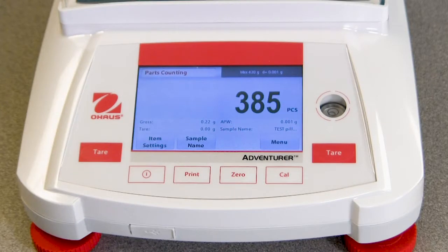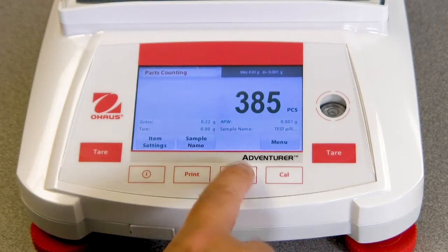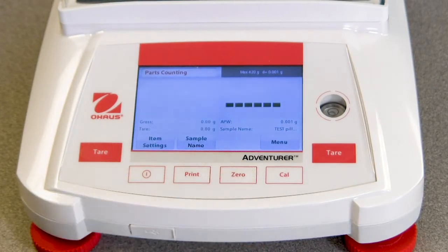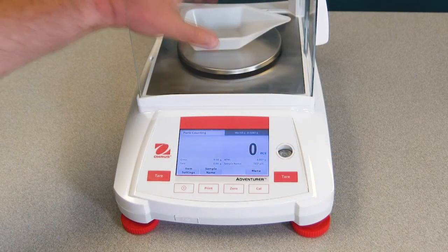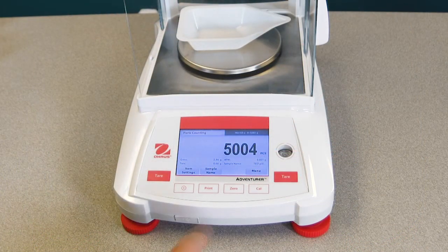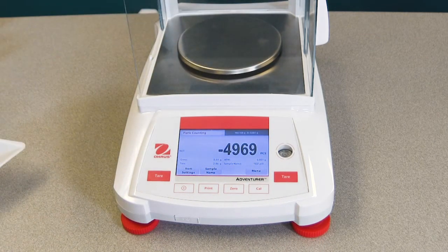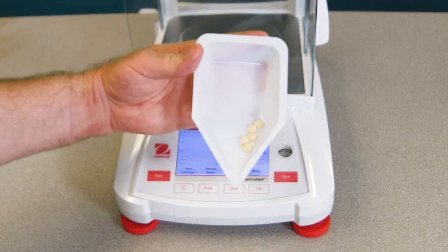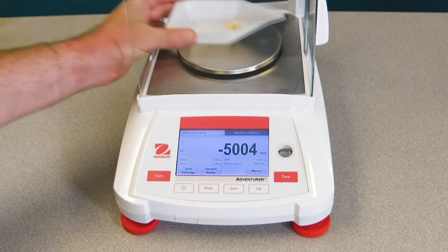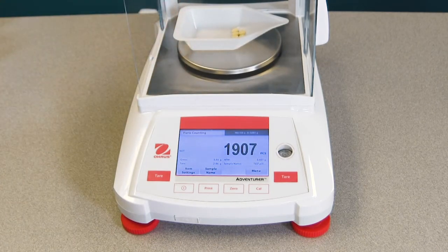If there is nothing on the pan but the balance is showing a result other than zero, press the zero key. If using a weighing container, place the empty container on the pan, then press tare, if the balance is not configured to auto tare. Remove the weight container and place a small sample of tablets in the weighing container. For this demonstration, I will place 5 in the container, then place back on the pan.